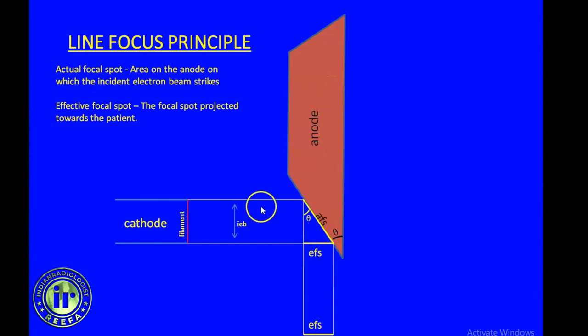The width of the beam should be longer so the surface area increases and there will be more heat dissipation. But if we have a wider beam, the image will be blurred. So we need a sharper image and higher heat dissipation. Both are contrary to each other. We need a trade-off between the two. That is achieved by the line focus principle.